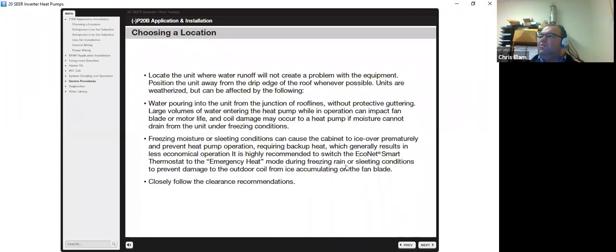It is important also to locate the unit where runoff will not create a problem with the equipment. Position the unit away from the drip edge of the roof whenever possible. The units are weatherized, but they can be affected by the following. You have water poured into the unit from the junction of roof lines without protective guttering. Large volumes of water entering the heat pump in operation can impact the fan blade, motor life, and coil damage may occur.